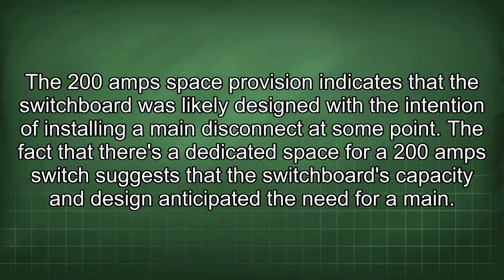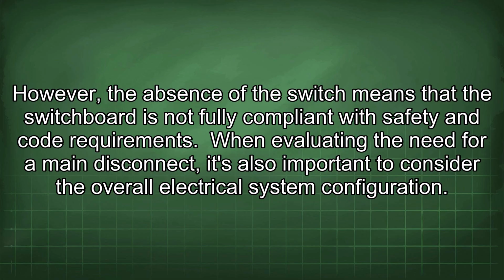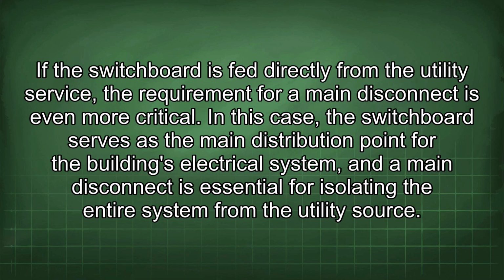The 200 amp space provision indicates that the switchboard was likely designed with the intention of installing a main disconnect at some point. The fact that there is a dedicated space for a 200 amp switch suggests that the switchboard's capacity and design anticipated the need for a main. However, the absence of the switch means that the switchboard is not fully compliant with safety and code requirements. When evaluating the need for a main disconnect, it's also important to consider the overall electrical system configuration. If the switchboard is fed directly from the utility service, the requirement for a main disconnect is even more critical.